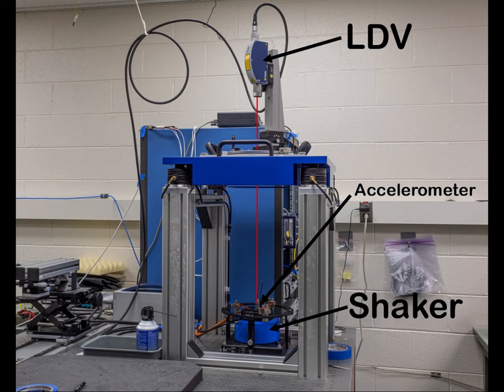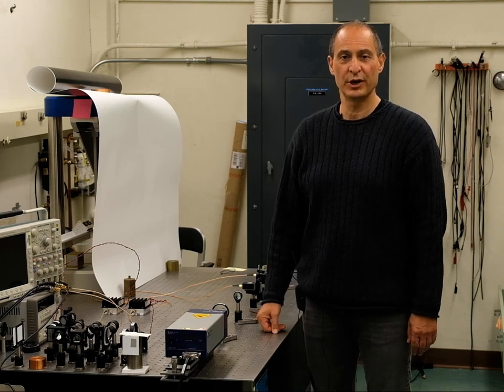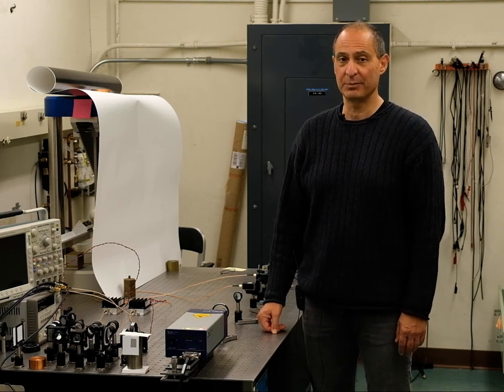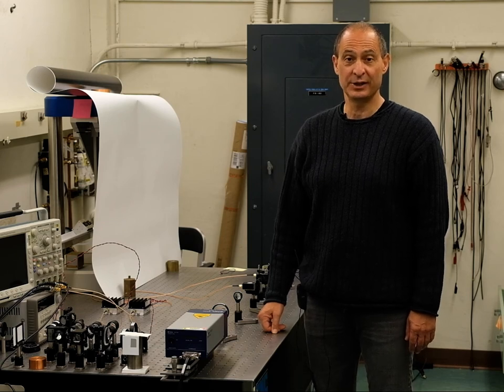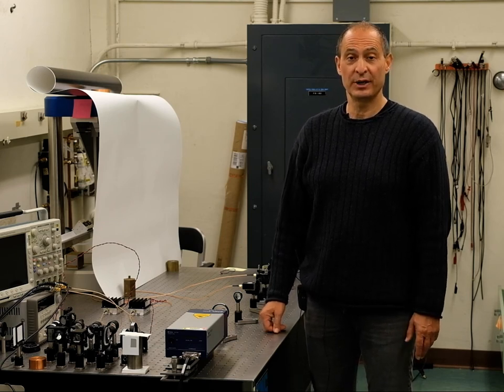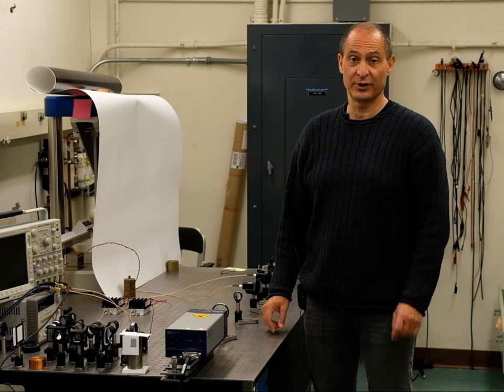So as you can see, the LDV is one of the main components used in the calibration of an accelerometer, and it in turn must be calibrated with a defined uncertainty traceable to the SI in order to calibrate the accelerometer with a defined uncertainty. In the national labs, we're constantly working on improving our calibration capabilities and decreasing our uncertainties. And so here's what the innovation is in terms of this work.